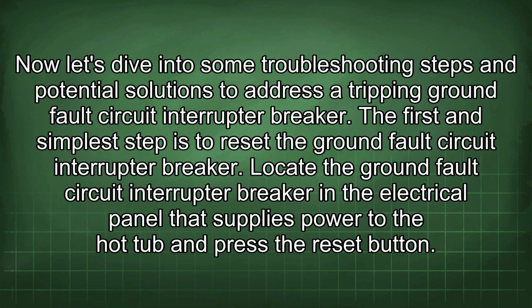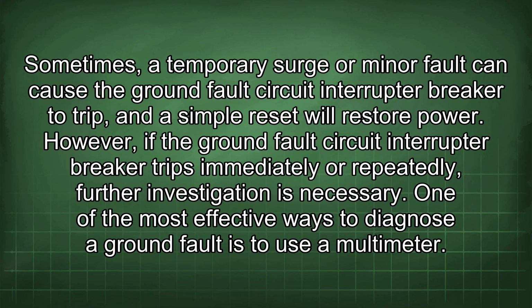Now let's dive into some troubleshooting steps and potential solutions to address a tripping ground fault circuit interrupter breaker. The first and simplest step is to reset the ground fault circuit interrupter breaker. Locate the ground fault circuit interrupter breaker in the electrical panel that supplies power to the hot tub and press the reset button. Sometimes a temporary surge or minor fault can cause the ground fault circuit interrupter breaker to trip, and a simple reset will restore power. However, if the ground fault circuit interrupter breaker trips immediately or repeatedly, further investigation is necessary.